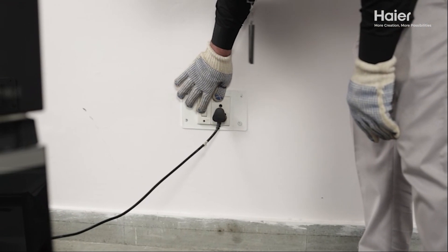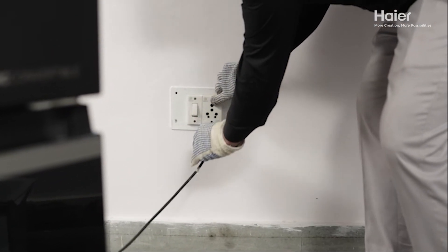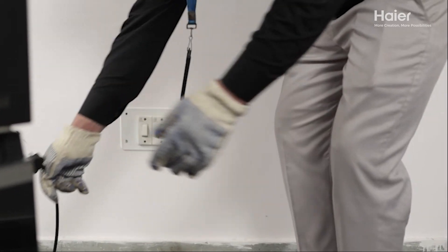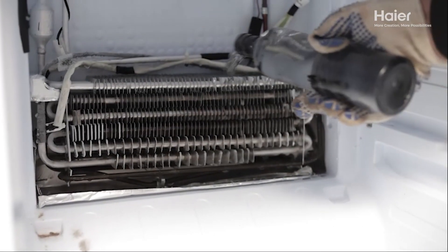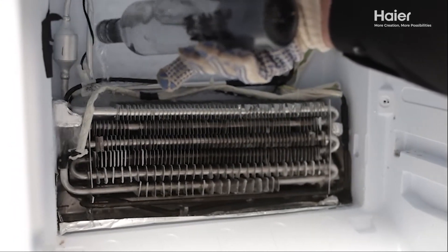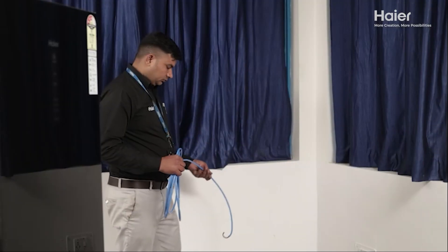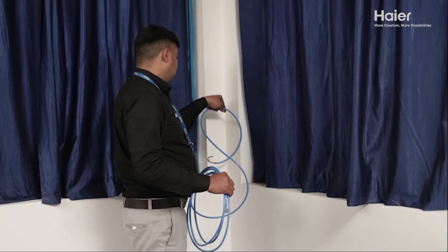Switch the unit to test mode for further repair work. Switch off the unit and disconnect the power cord from the electric board for safety. Clean the evaporator thoroughly with water to remove any frost and moisture accumulation. Use tube pinching pliers to clamp the charging tube port and release the gas from the system through a window or door.